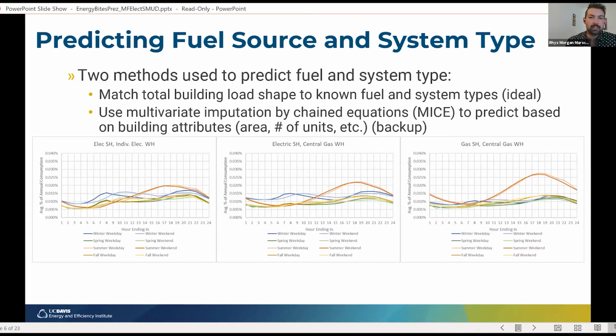So I used two methods to predict the fuel and system type of each building. The first, the ideal solution, is to match total building load shapes for buildings where we don't know the fuel or system type to buildings where we do. At the bottom, you'll see different examples of average load shapes for buildings with electric space heating and individual electric water heating. Because of electric water heating, you get a higher base load, since water heating runs more consistently than space heating. Whereas on the right, you've got an all-gas building where your main variable load is air conditioning. Matching those up is the ideal way to identify what fuel types are in different buildings.